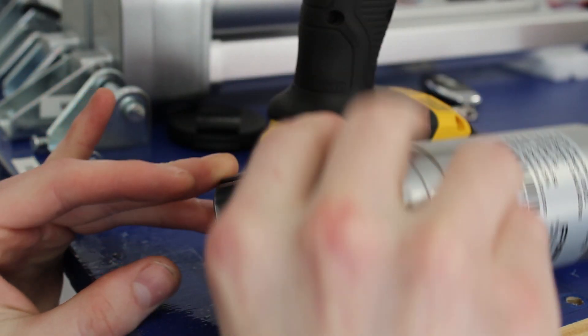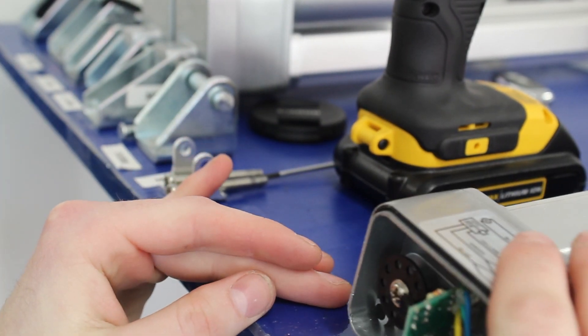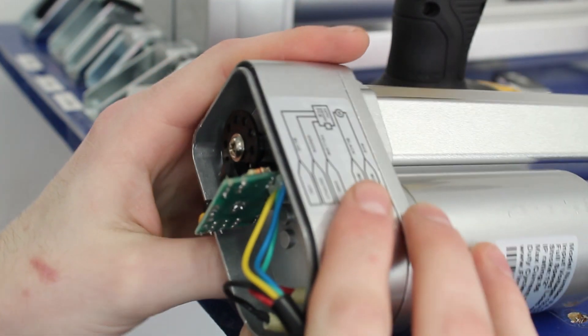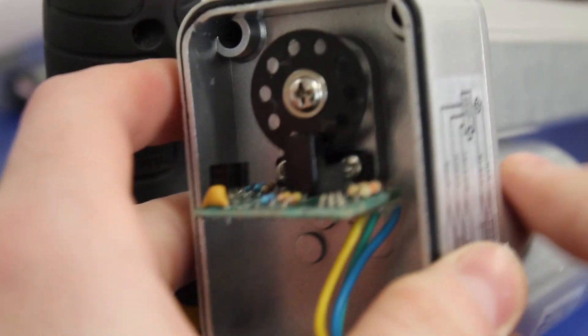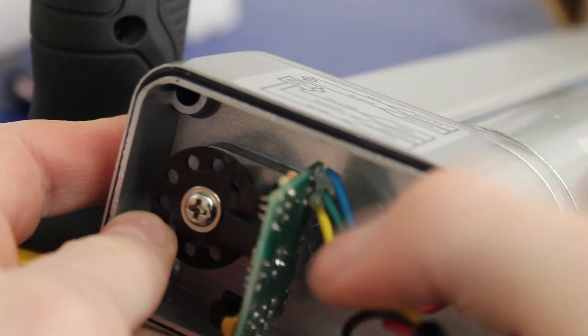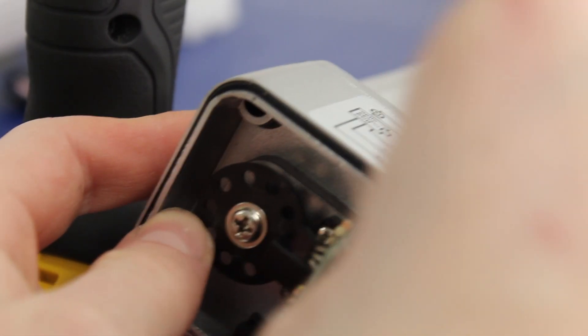The green, blue, and yellow wires are the ones for the sensor. The red and black just feed the motor. So examine your optical encoder wheel for debris or damage. Sometimes they can rub. That'll cause plastic shavings to get all over the sensor area, and that can keep it from reading. This one doesn't have that problem.